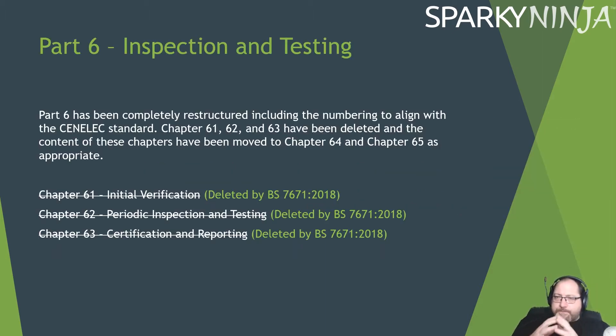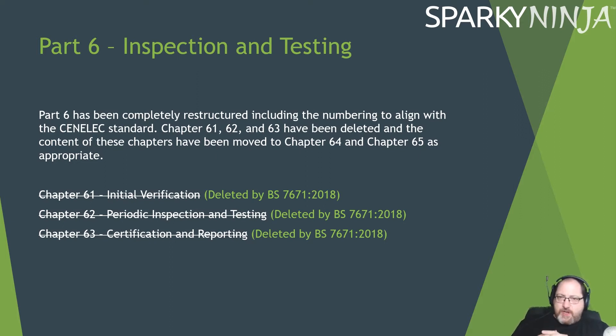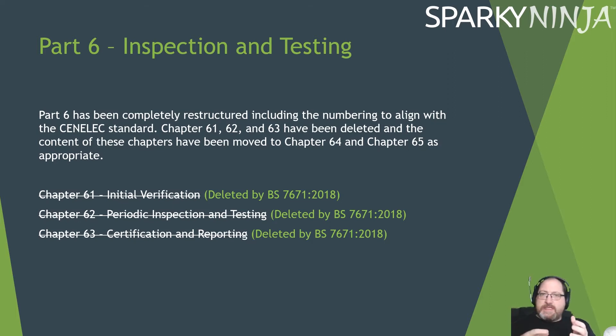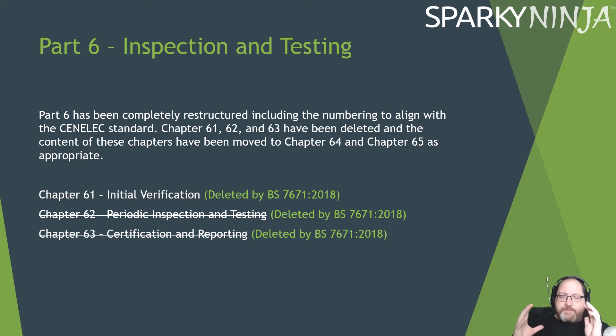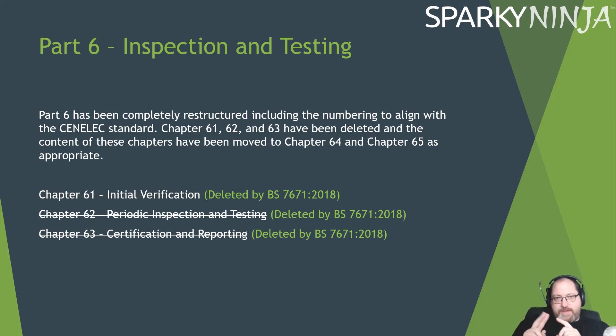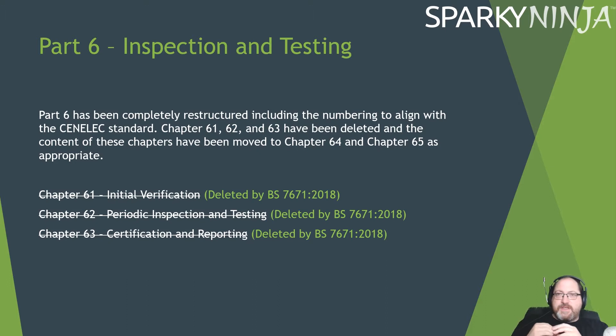It's been completely restructured to align with CENELEC now. What we had before was Chapter 61, 62, and 63. 61 was initial verification, 62 was periodics, and 63 was another chapter all about certification and reporting. What they've done is taken those three out, and we now have Chapter 64 and 65. The certification has been split and included with initial verification and periodic inspection testing respectively.